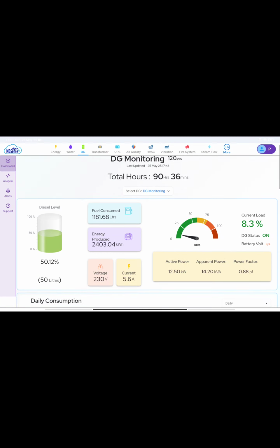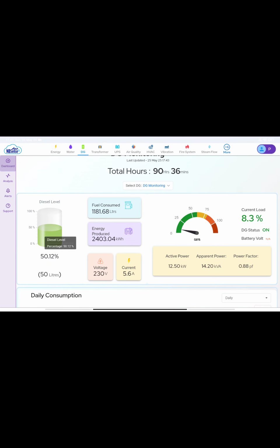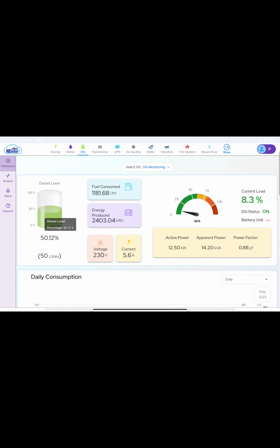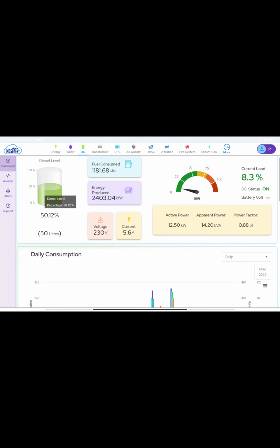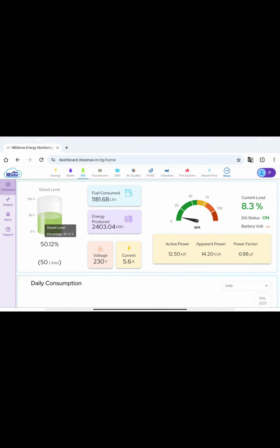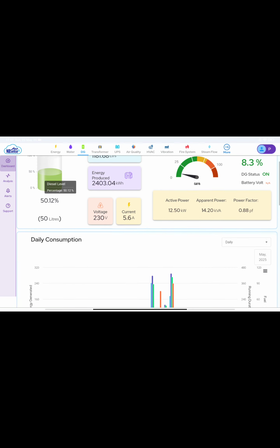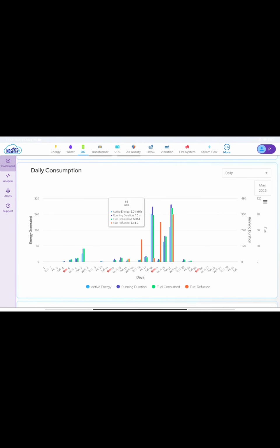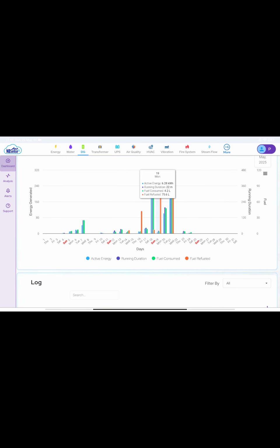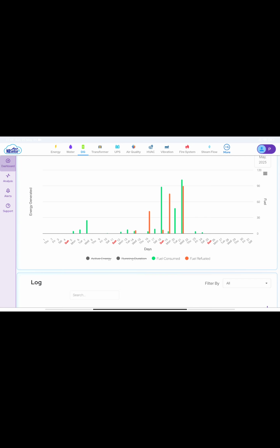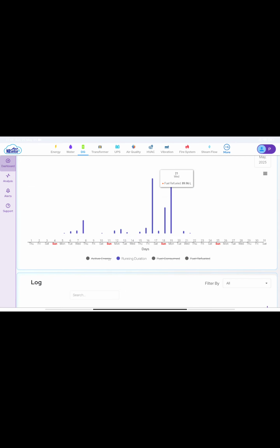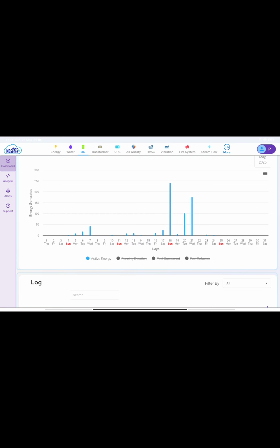The next product we have is diesel generator monitoring. Our platform is able to give milliliter-level fuel accuracy. Here we can see the real-time fuel level, total fuel consumed, and energy produced. If the DG is on, we can see the current load, active power, apparent power, power factor, voltage and current. In a month, day-wise history is available showing how much fuel was added, how much was consumed, and how long it ran. Any specific parameter can be seen by selecting and deselecting.